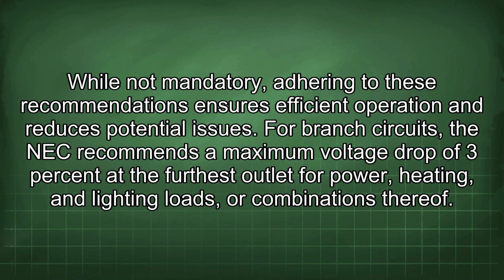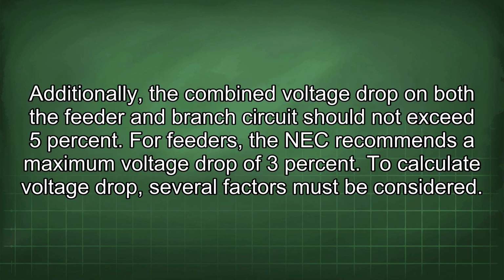For branch circuits, the NEC recommends a maximum voltage drop of 3% at the furthest outlet for power, heating, and lighting loads, or combinations thereof. Additionally, the combined voltage drop on both the feeder and branch circuit should not exceed 5%. For feeders, the NEC recommends a maximum voltage drop of 3%.